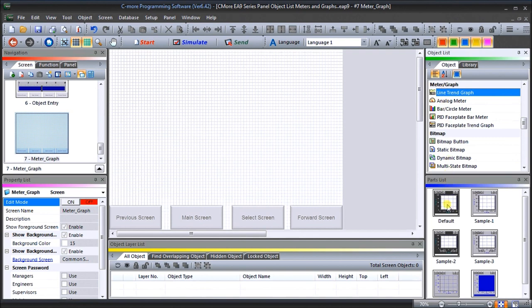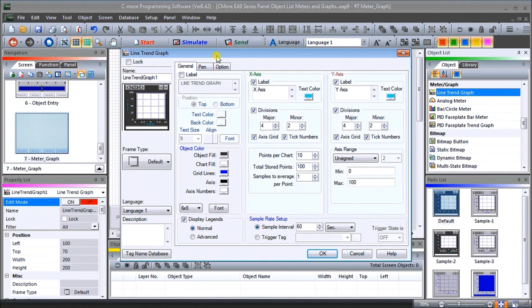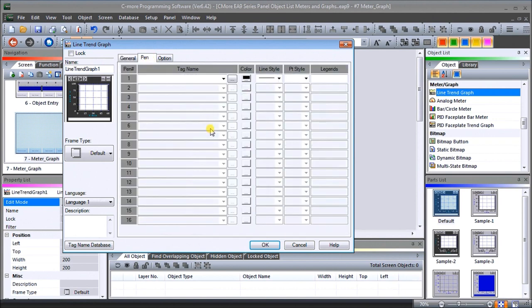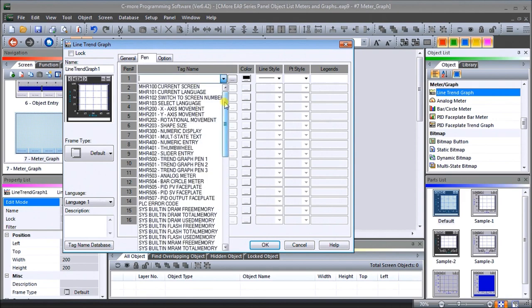We'll take the default trend line and drag it out to our screen to bring up the line trend graph window. Under the points on our graph, we'll change from 10 to 60, and our sample rate we'll change to one second. We'll leave everything else the same. You can also change the x-axis or y-axis to change the look and feel of those parameters. Under pens, we can have up to 16 pens on our graph. I've already pre-programmed the pens — here's graph pen number one.